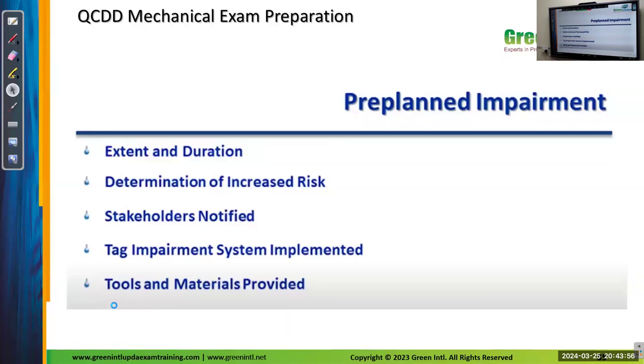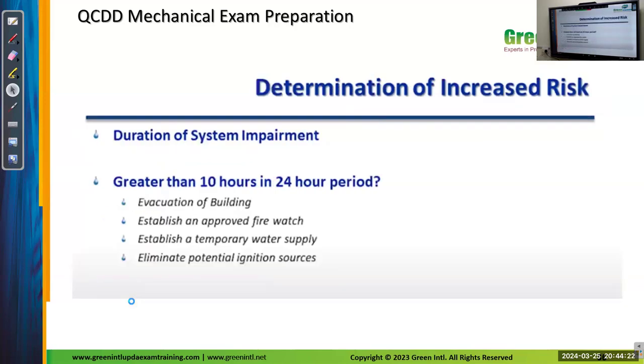And for pre-planned impairments, you have to mention in the pre-planned impairment form how long it will extend. What are all the risks you identified, whether stakeholders have been notified or not, tag the impairment system to show whether the system is working or undergoing the maintenance process, and tools and materials provided. For duration greater than 10 hours in a 24-hour period, you have to evacuate the building, establish a proper approved fire watch, establish a temporary water supply system, and eliminate potential ignition sources.